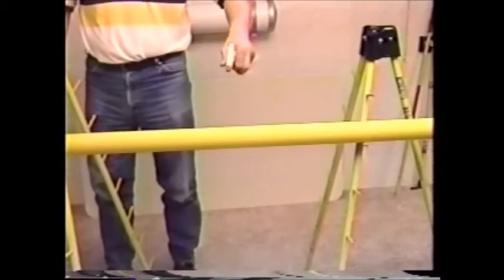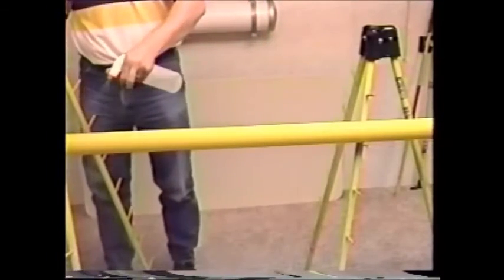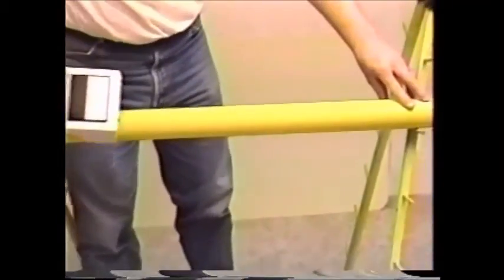The tool being tested should be wetted until the water just starts dripping. Set the tester for the wet test and zero the meter. Place the tester on the stick and observe the meter. Lift the tester, move down the stick, and take a second reading. Repeat this process until the entire stick is tested.